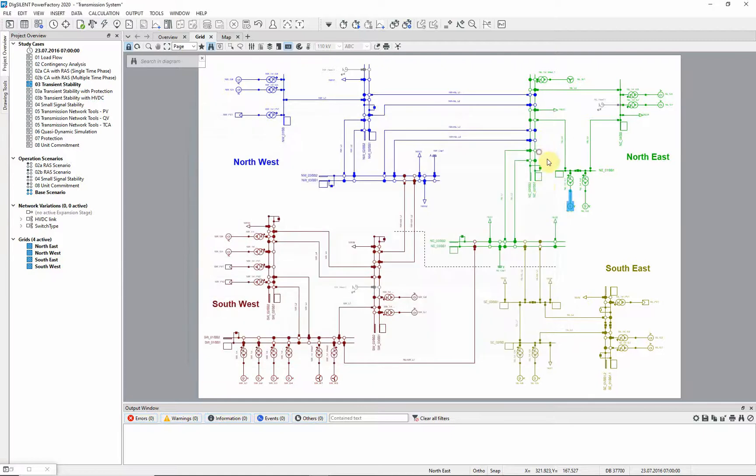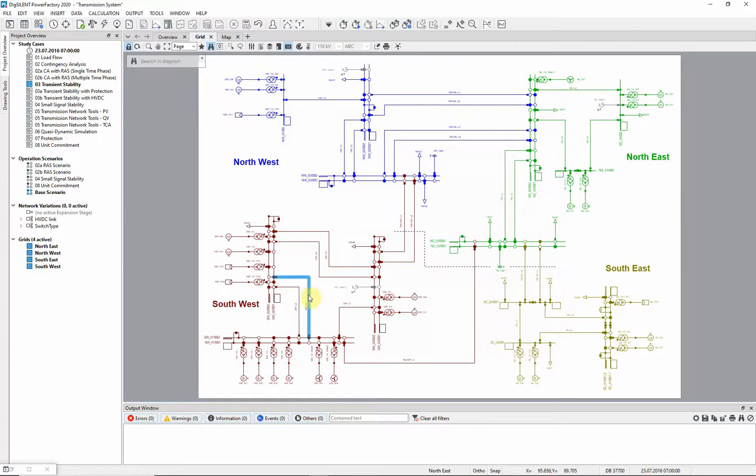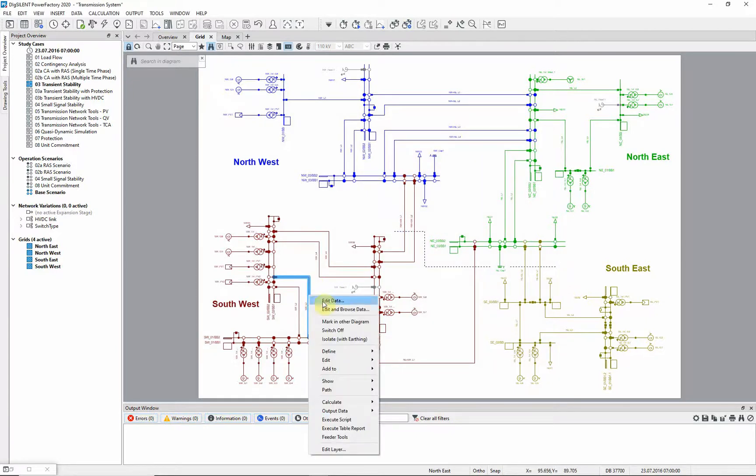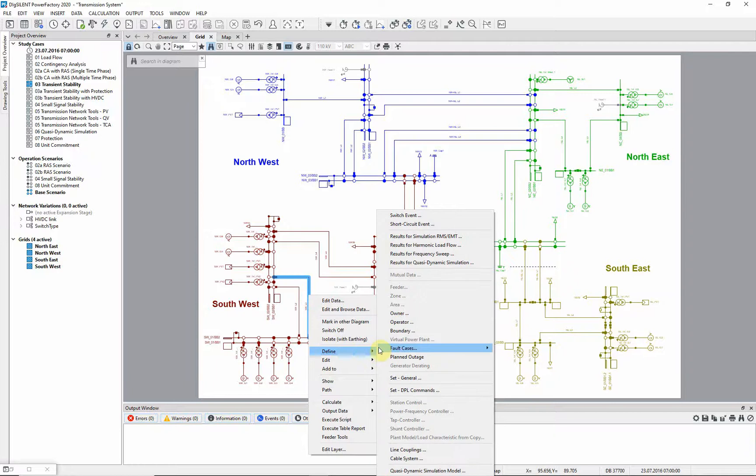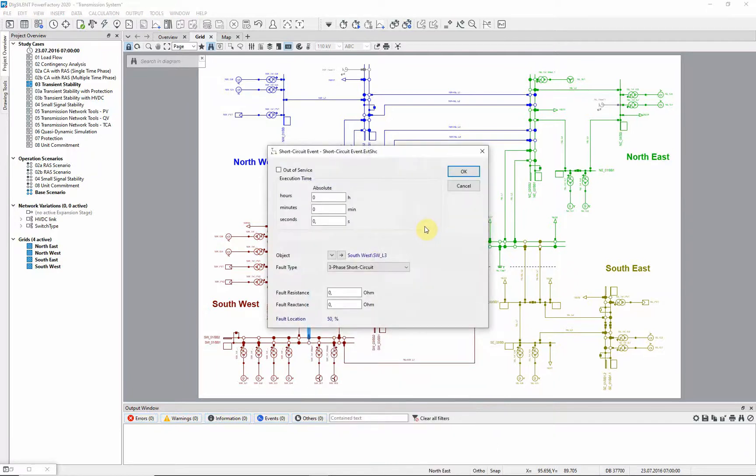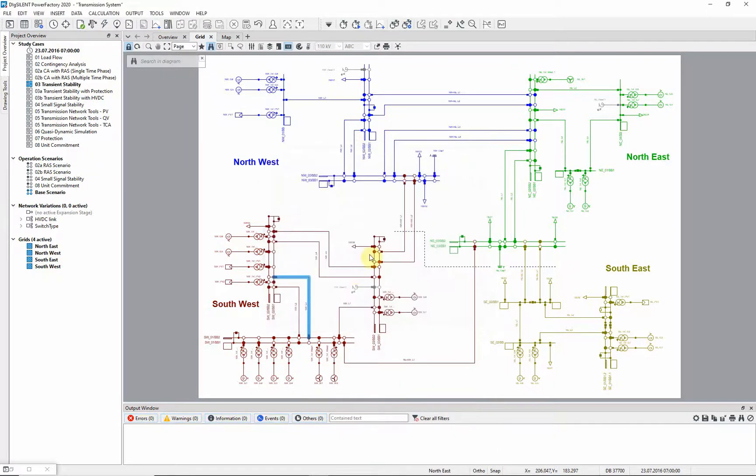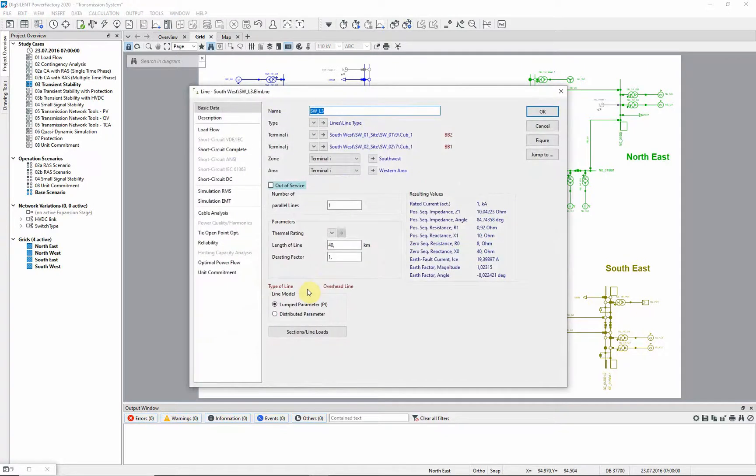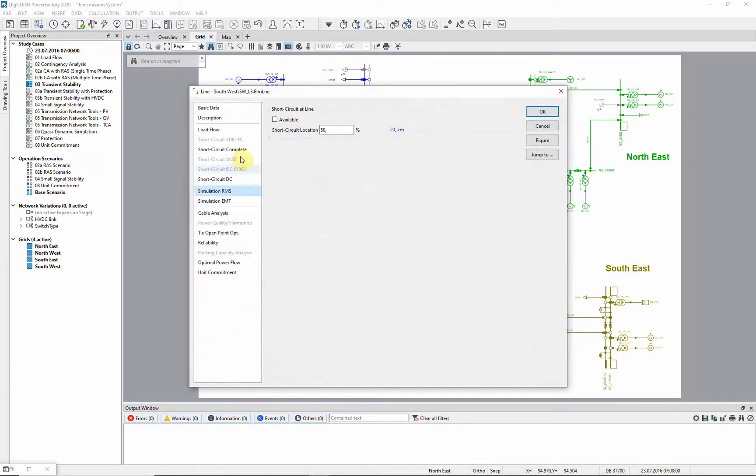First, we need to set up the events for the simulation. We will study a fault on the line SWL3. Right click on the circuit from the grid graphic and define short circuit event. We must also make sure that this event is available for the RMS simulation. To do this, edit the element, go to the RMS simulation page, and ensure that the available box is checked.